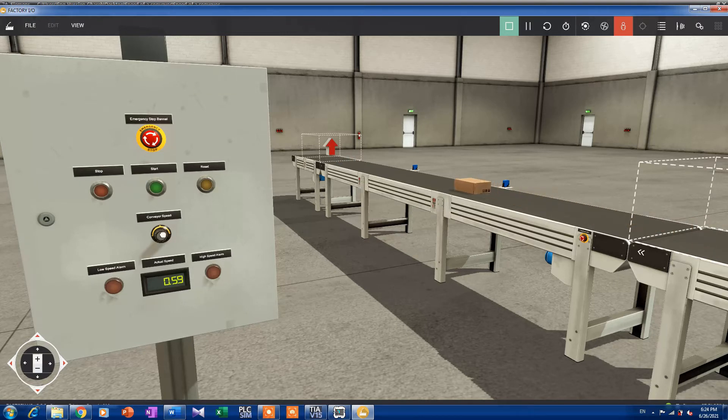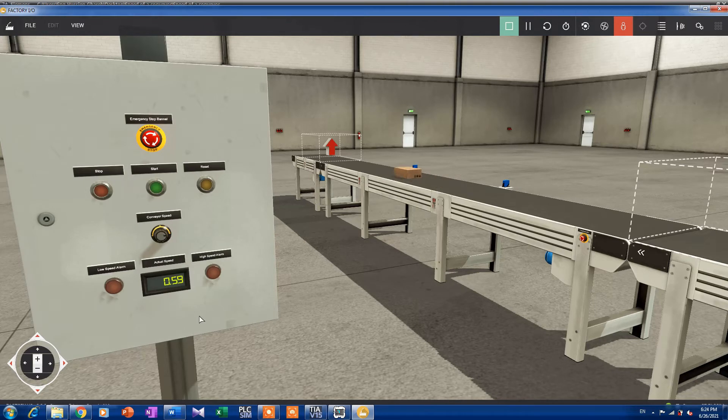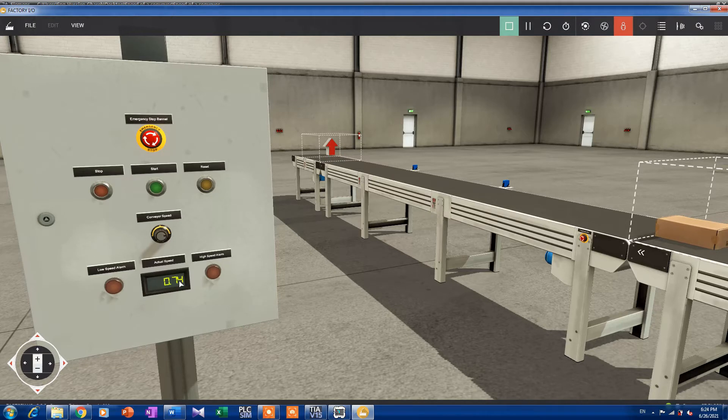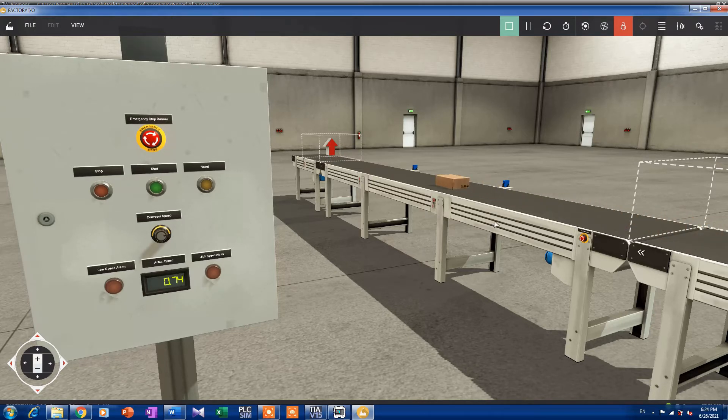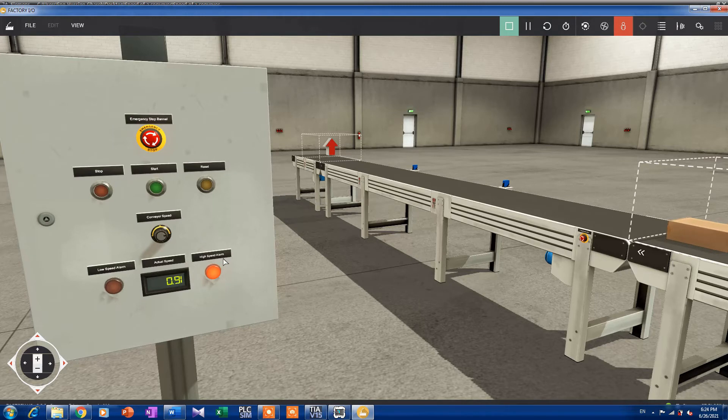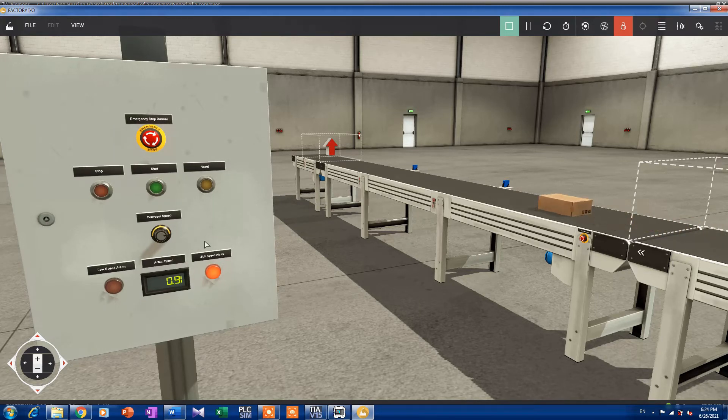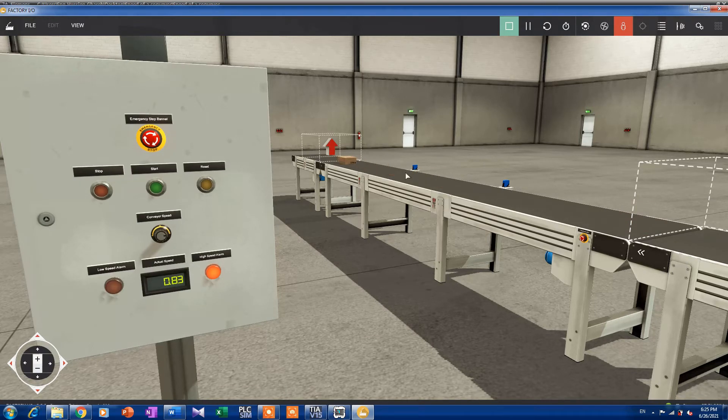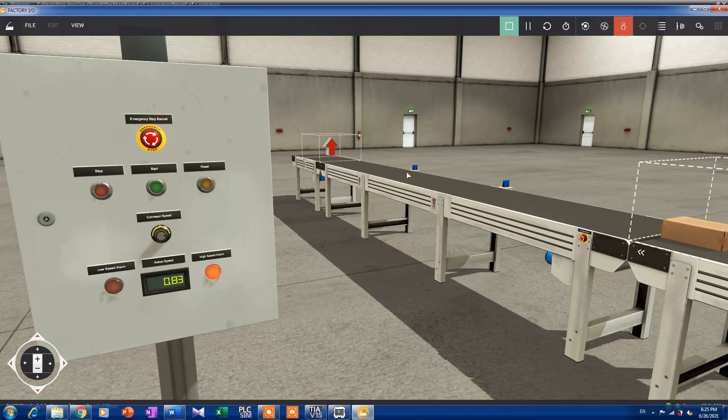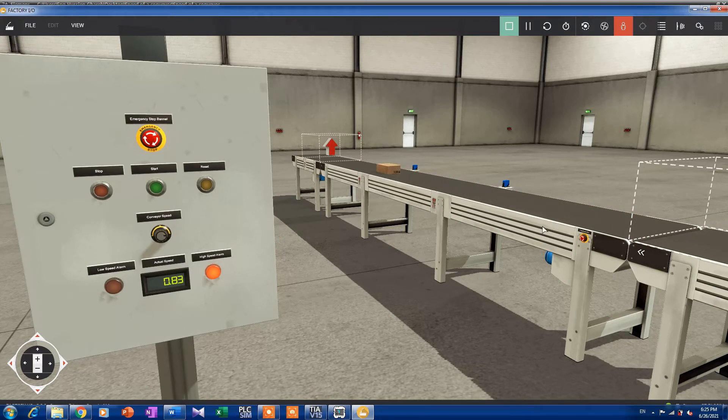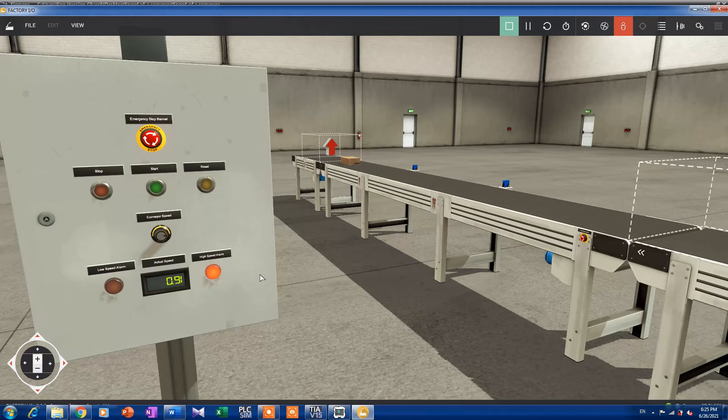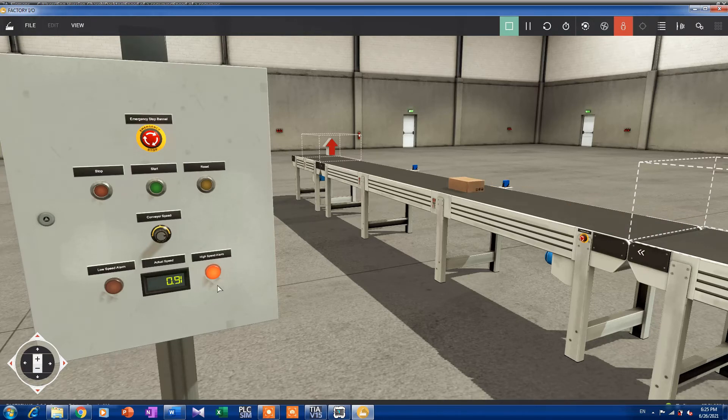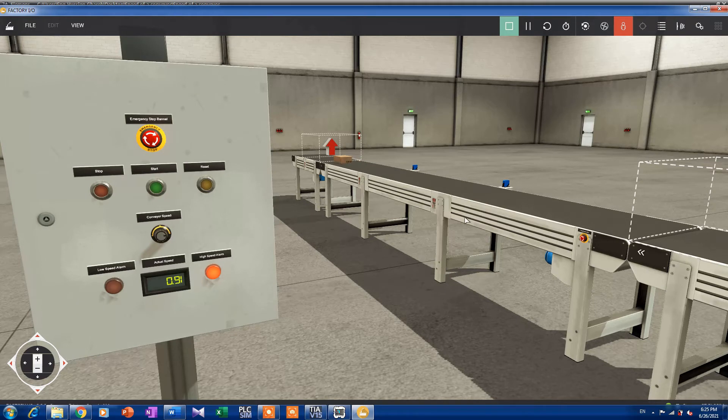Let's try to make it faster. We can see that the speed is increasing, 0.74, and now it's 0.9. And we have a high speed alarm, and that's what we want. That's what we need. When any change happens in the system, when any simple change happens in the speed of the conveyor, we want to take a feedback for that.